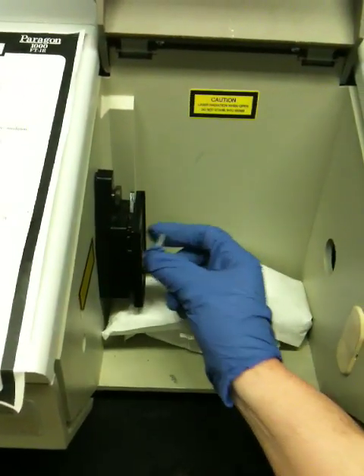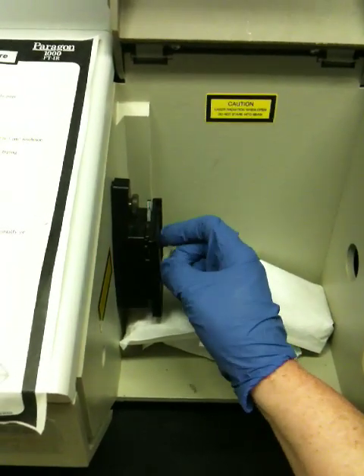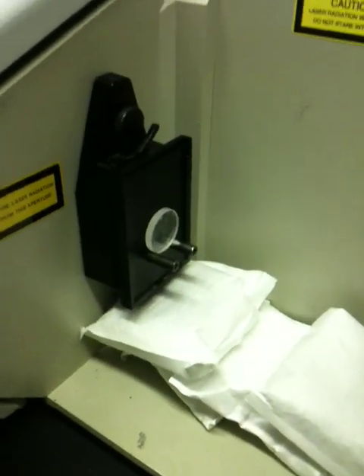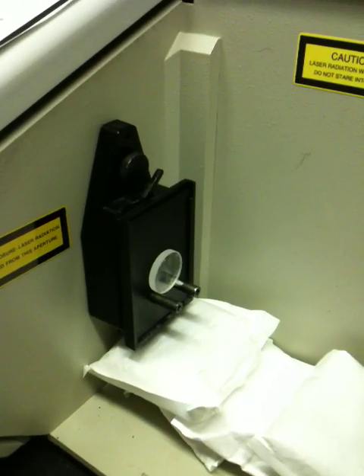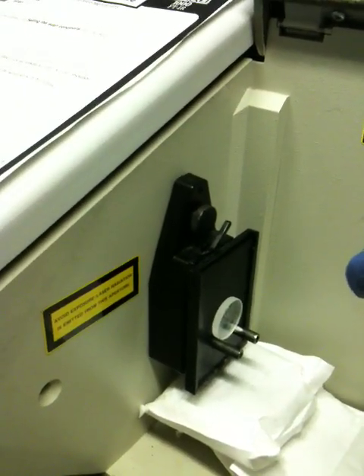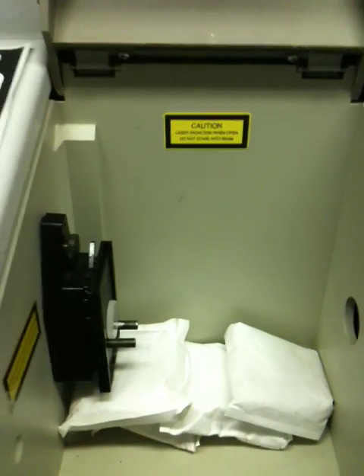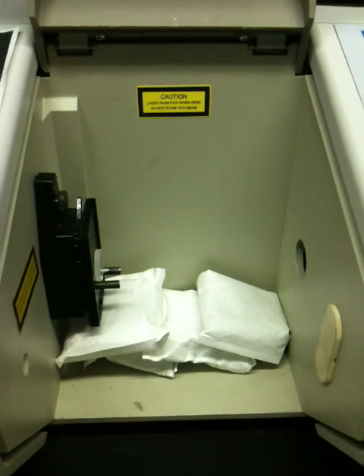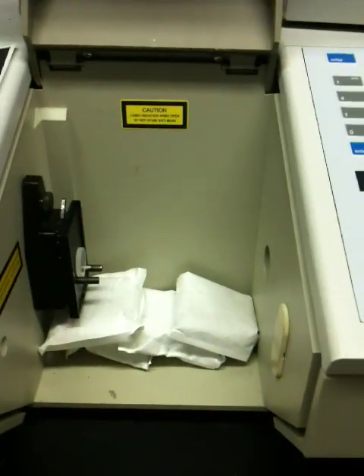I'm going to put it on the prongs in the sample holder. So the cell goes up on these prongs. Students always ask me, which way do you put it in? I say, put it in so that the sample's on the outside so you don't contaminate the instrument. Right now it's kind of like an open Oreo cookie or an open sandwich cookie, right? It's like when you twist the Oreo open, you've got the cookie and you've got the icing on it. That's what it's like right now. You want the icing on the outside.